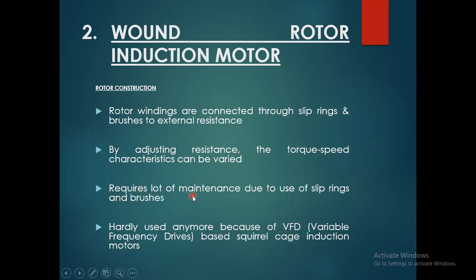So this is the main thing: it requires a lot of maintenance due to the use of slip rings and brushes, because the brushes are continuously rubbing on the surface of the slip rings. Due to this wear and tear and friction, the carbon brushes continuously rub and wear away at some point, so we have to replace the carbon brushes with new ones, and also maintain the surface of the slip rings which rub against the carbon brushes. That's the main cost involved in slip ring induction motors.